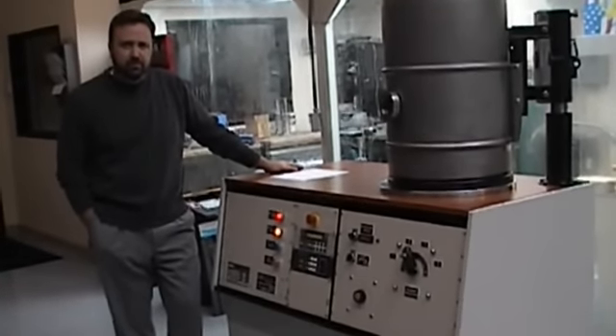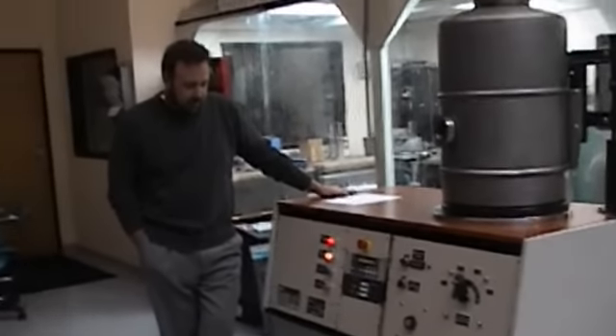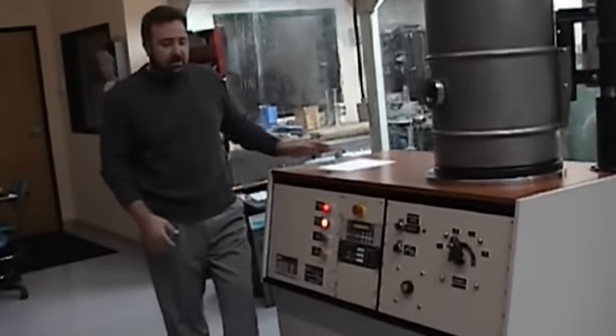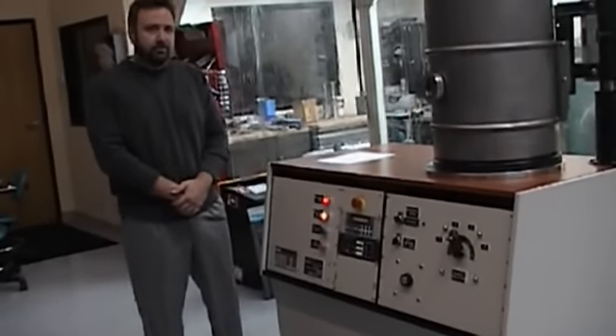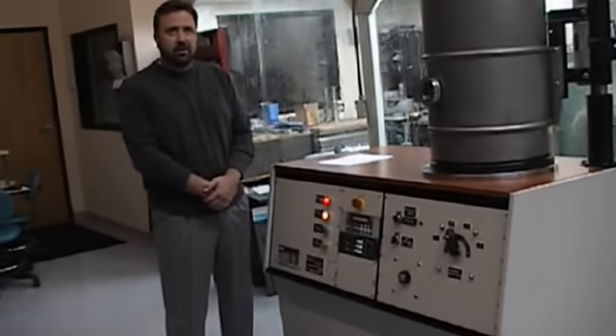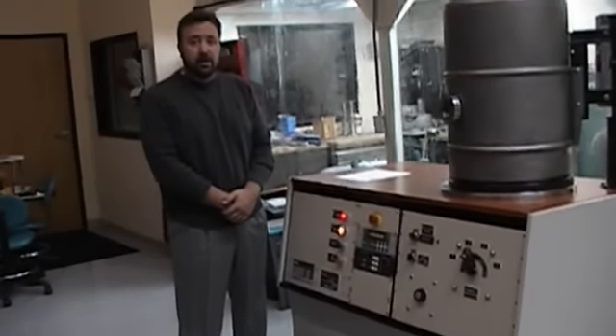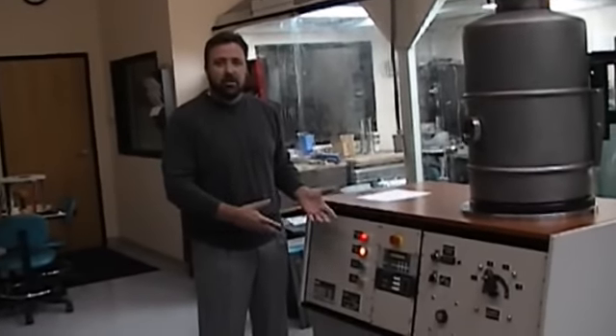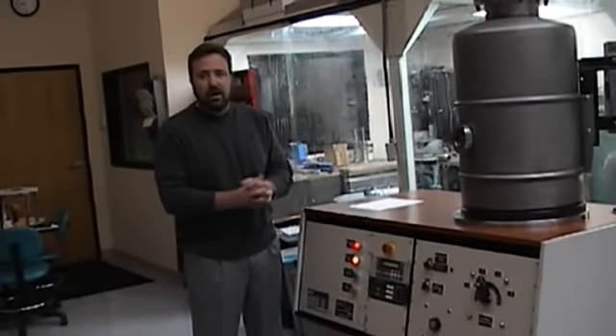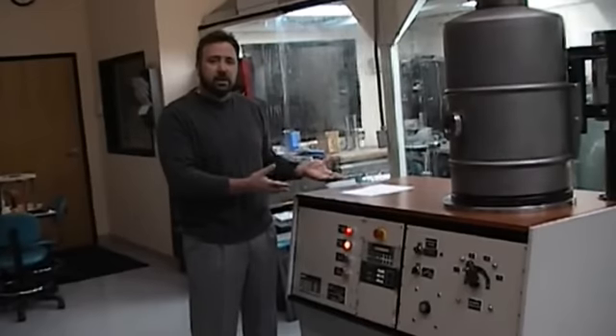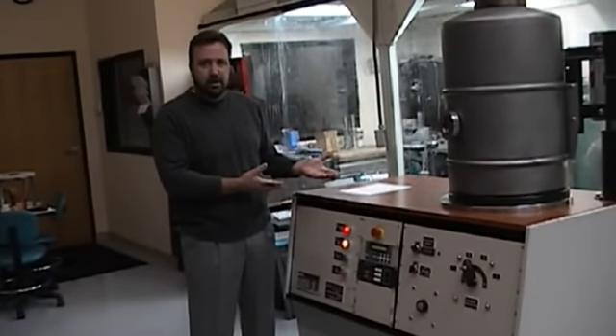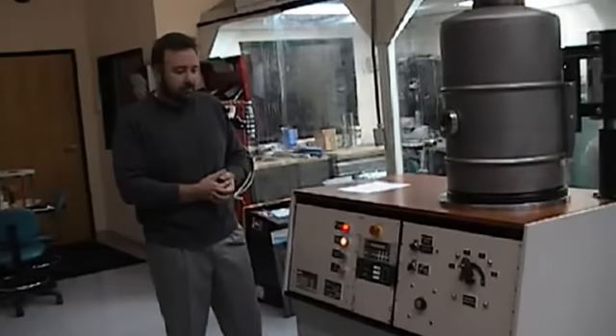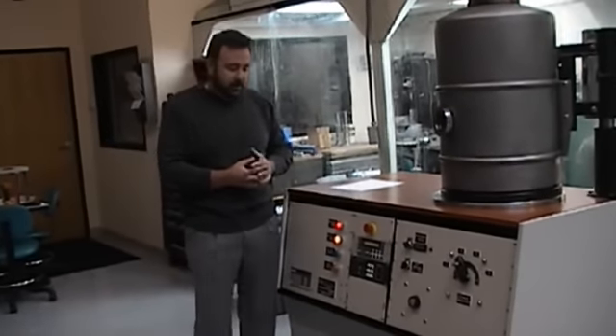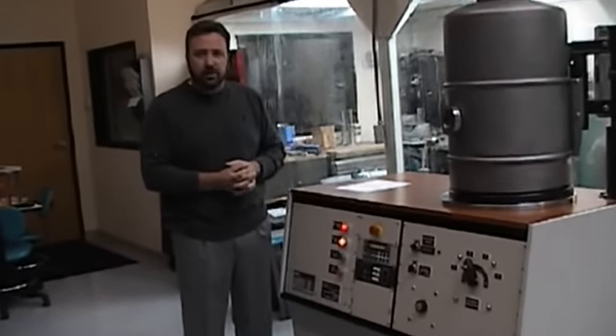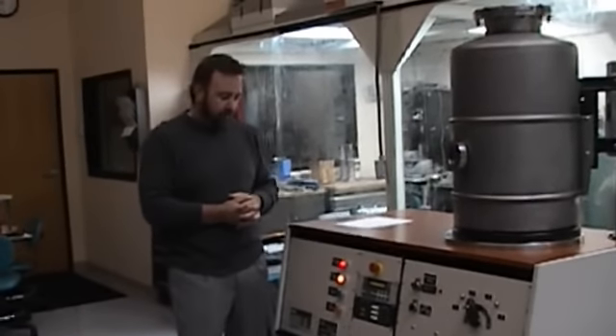I think our pump down cycles were about 2 to 3 minutes. 2.5 minutes. 3 minutes. And that is to a crossover pressure of, I believe it was 1 times 10 minus 1, which would be roughly 100 millitorr. We recommend at least 100 millitorr crossover. You can go a little bit higher. It'll increase the requirement for the regeneration times between the cryo pumps. So use the 100 millitorr as a benchmark. I think you'll be okay.